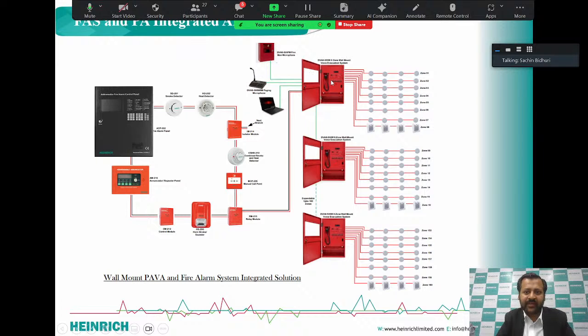with the help of which we can have an automatic announcement in different zones, or different announcements. Suppose there is a building of 10 floors and a fire has started on the second floor, then we can have an automatic announcement of evacuation on the second floor. But after a delay of some seconds, we can have an announcement of alert on the alternate zones or alternate floors from where the fire has started.